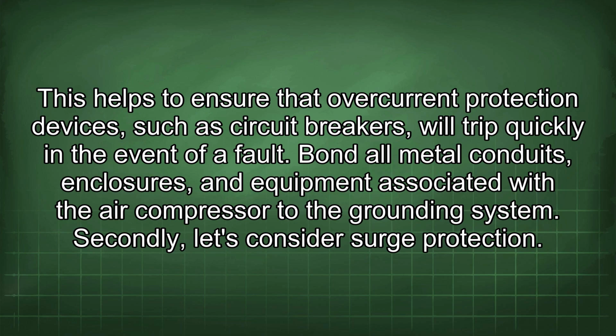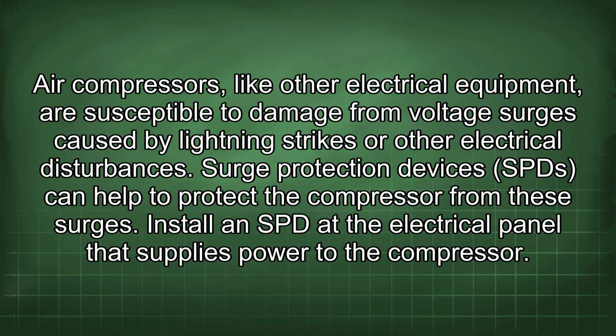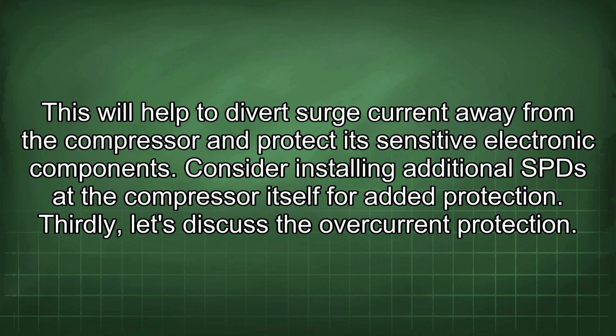Secondly, let's consider surge protection. Air compressors, like other electrical equipment, are susceptible to damage from voltage surges caused by lightning strikes or other electrical disturbances. Surge protection devices (SPD) can help to protect the compressor from these surges. Install an SPD at the electrical panel that supplies power to the compressor. This will help to divert surge current away from the compressor and protect its sensitive electronic components. Consider installing additional SPD at the compressor itself for added protection.